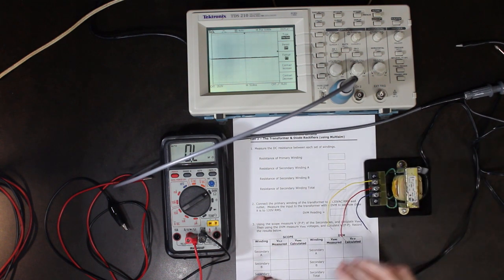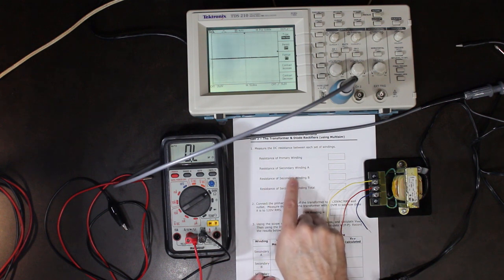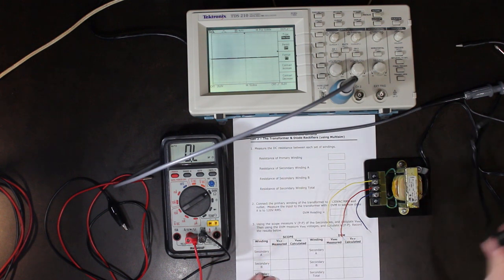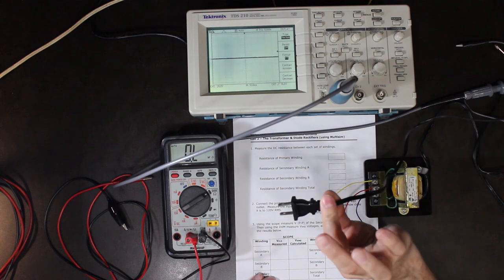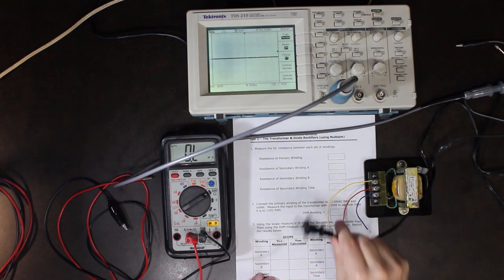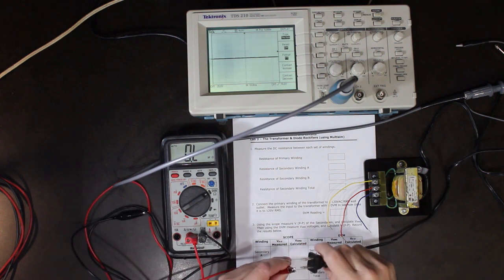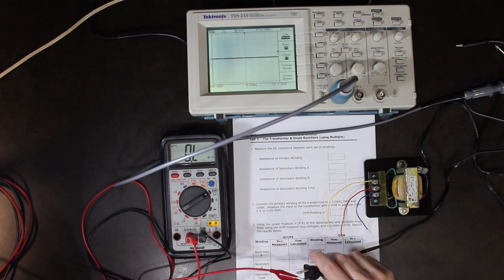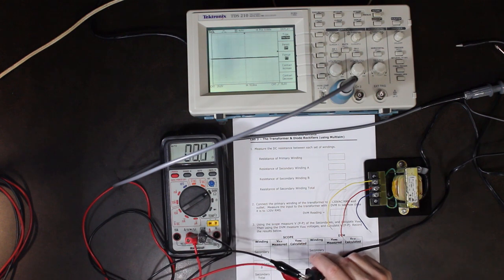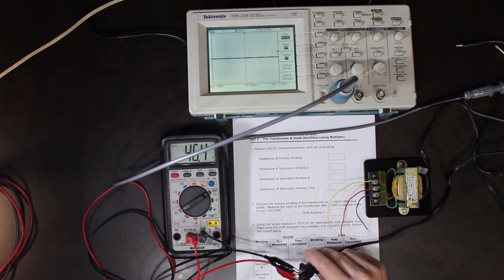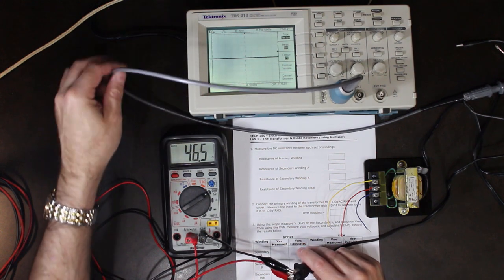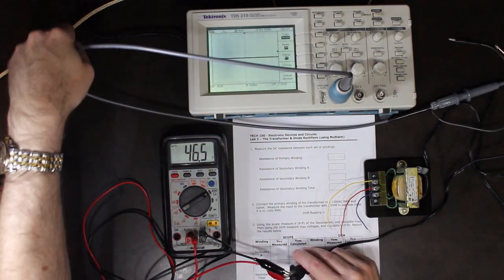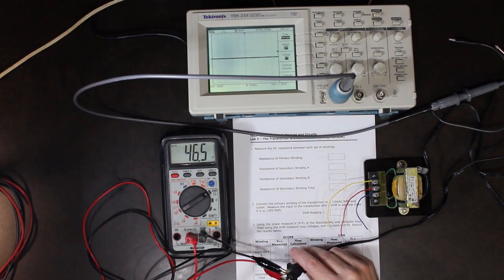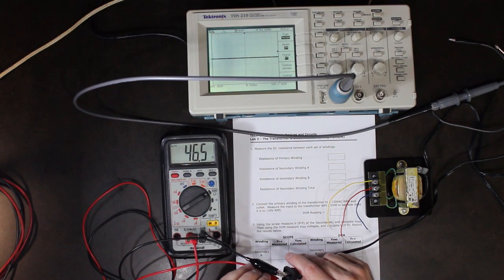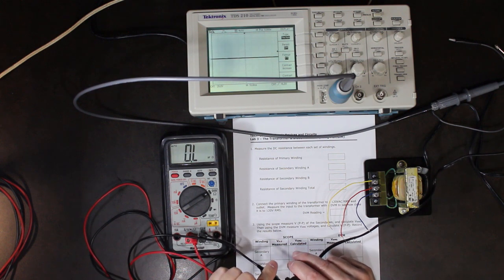The first thing it's going to ask us to do is measure the resistance of each of the windings. This plug is connected directly to the primary side, so I'm just going to measure the resistance. The resistance is 46.5 ohms. Let's move this probe out of there so you can see. 46.5 ohms. So that is the resistance on the primary side of that transformer.